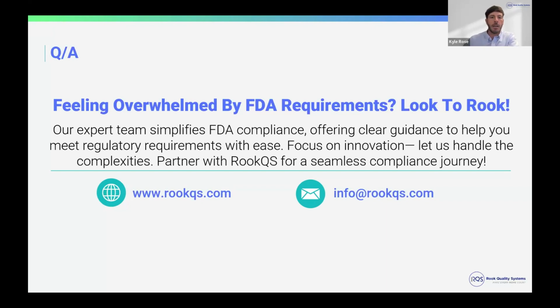So some of the things around how reporting should be done, how it should be presented in regulatory submissions to the FDA, how they want labs to work together and have similar reporting procedures using similar references, things like that, I think are also the scope of the guidance that are outside of specifically the 10993 standard. So when you are going through the process of identifying what chemical analysis testing you need to do, you should be referencing both the standard itself for compliance to the standard, but also the guidance to make sure any other additional things that are called out in the guidance are met with your device.